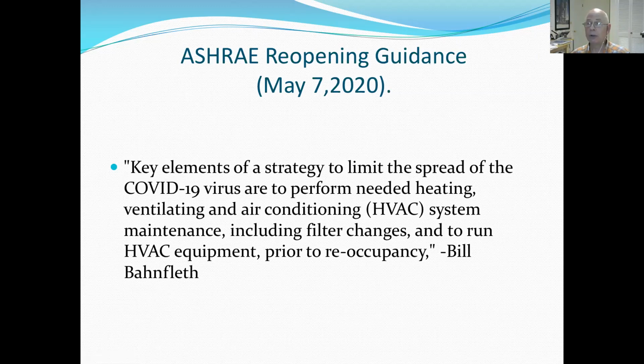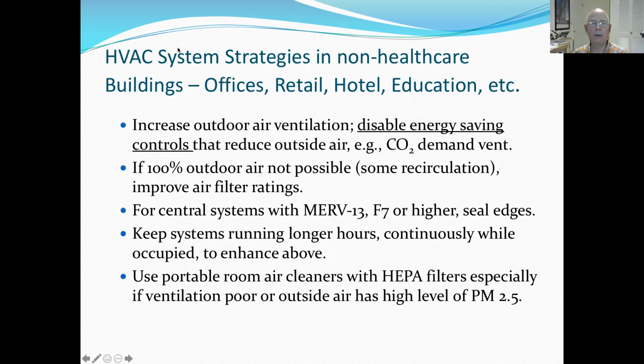Do you know that all your systems are actually turned on? Do you know the outside air dampers are really open and delivering what they're supposed to? Do you have any way of verifying that with air balancing equipment, or can you get someone in to do that? Do you have some flow hoods to make sure that the diffusers in the ceiling are really flowing air, that a fire damper hasn't shut, that a duct hasn't been clogged up with debris? So are you sure your system is running? Are you doing the proper filter changes and getting the outside air in there?